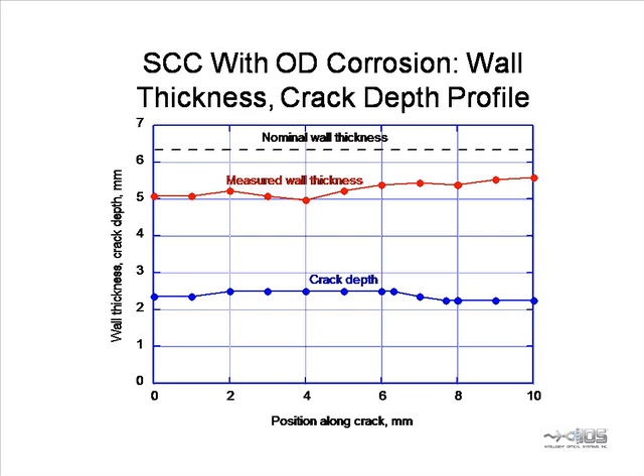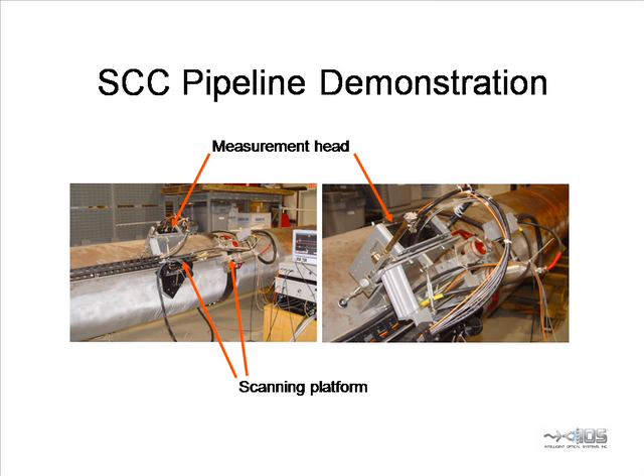We scanned another crack at a position where there was significant OD corrosion. We were able to measure the wall thickness along with the crack depth. This enables a realistic determination of the crack depth as a fraction of the remaining wall. We participated in an industry demonstration of a scanning laser ultrasonic system in Houston, Texas. A measurement head was mounted in a motorized platform that could be scanned axially and circumferentially. Since the cracks were mostly axial, this was the common scan direction.